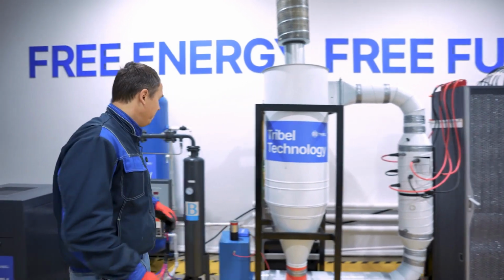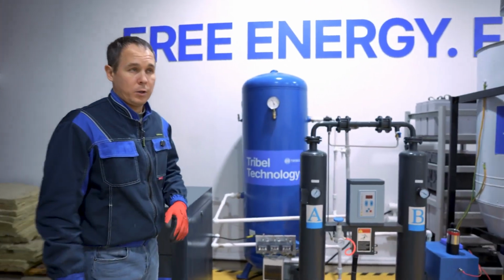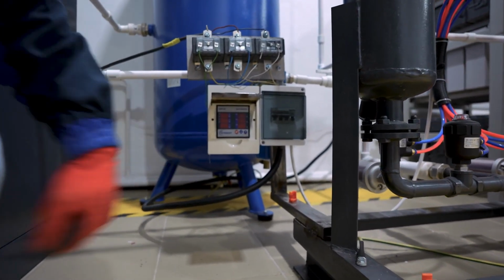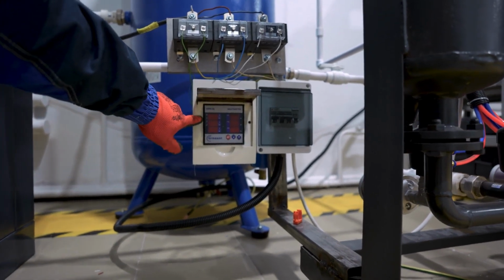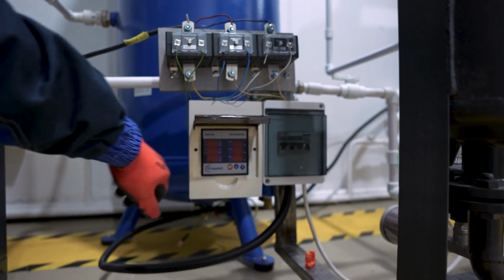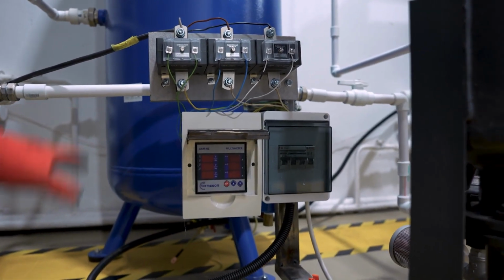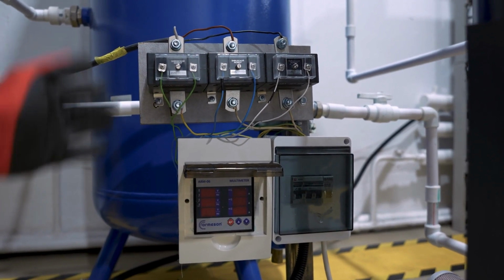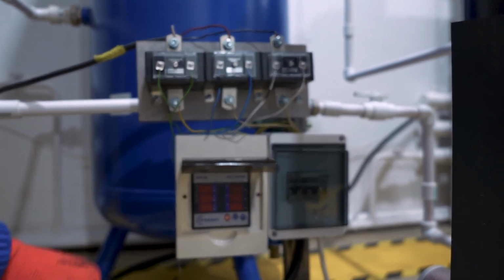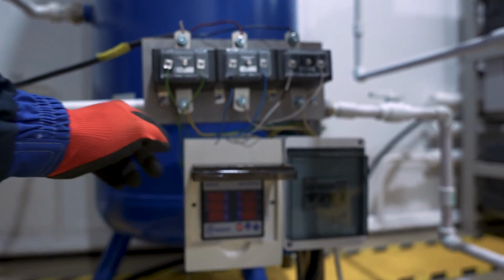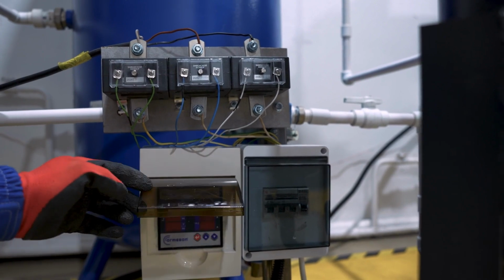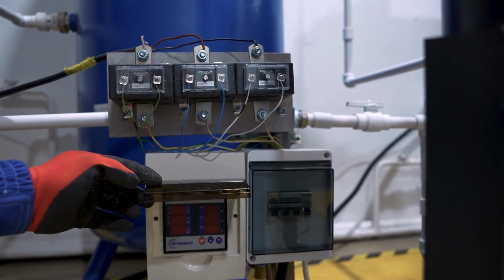Come with me. In this configuration, we have installed an integrated ammeter. This device will provide a clear reading of the network voltage in volts, while simultaneously showing the flow of electrical current in amperes. This is the electricity consumption. We have also installed current transformers here. These components are essential so that our ammeter can display accurate readings. Each current transformer comes with its own official calibration certificate. We will also make sure to include it in the final project documentation.